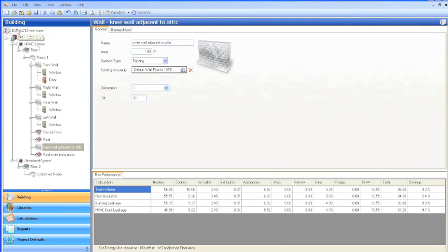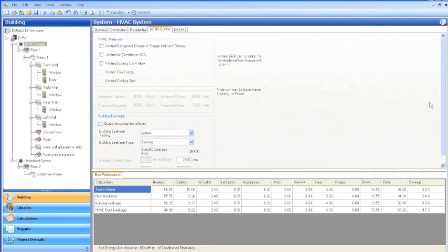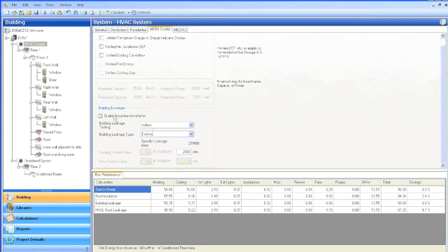Okay. We had a couple folks ask, on the HVAC system, could we go through the HERS credit tab again? Certainly. Let's look at that a little bit more. Notice that this is where you are indicating the leakage in the building envelope. As part of the Energy Upgrade California program, when you do an assessment on an advanced job, you are required to do a blower door test on the house to get infiltration values. And so that is what you're entering here, the CFM50 from that reading.